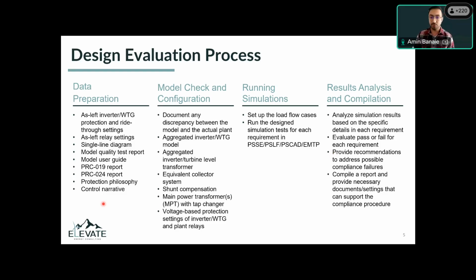So for PRC-019, there are a few items that are required and very necessary to be able to even start an evaluation of the plant. And that would include, firstly, the as-left settings of the voltage and frequency protection across the plant. And that would include the inverters, the relays on the HV side of the MPT, feeder relays, substation relays, if there are any shunt reactors or cap banks, undervoltage, overvoltage elements. All those settings are required for a PRC-019 study.